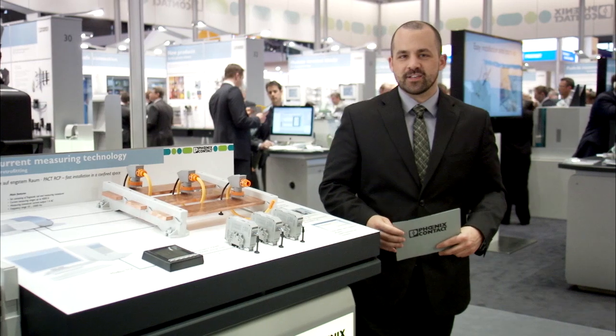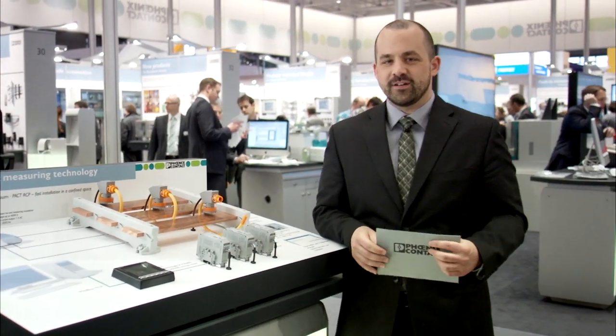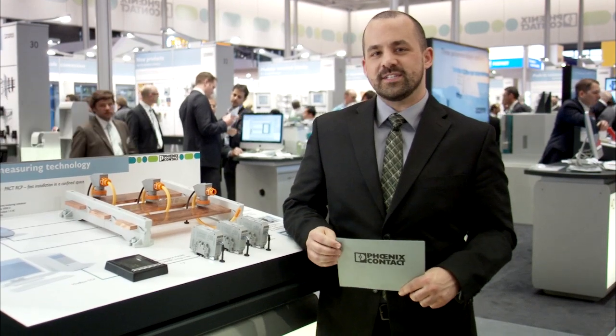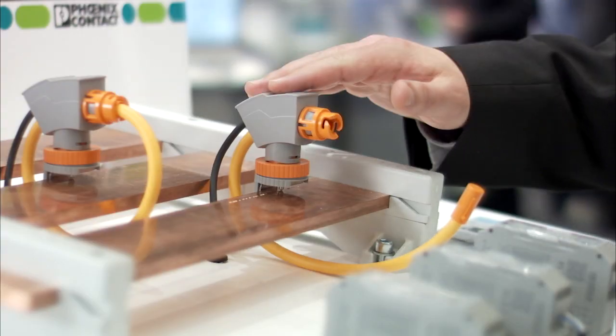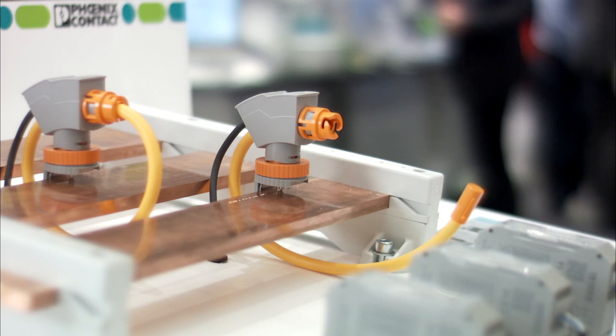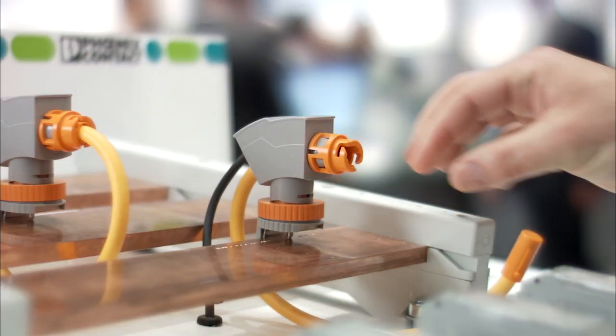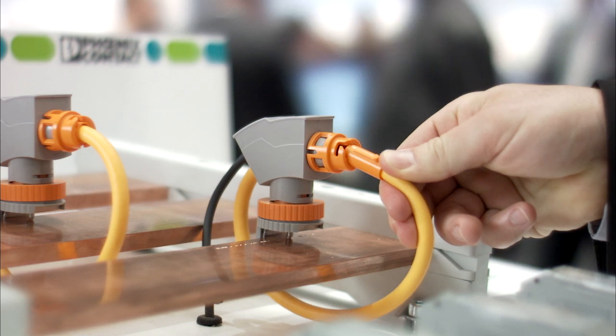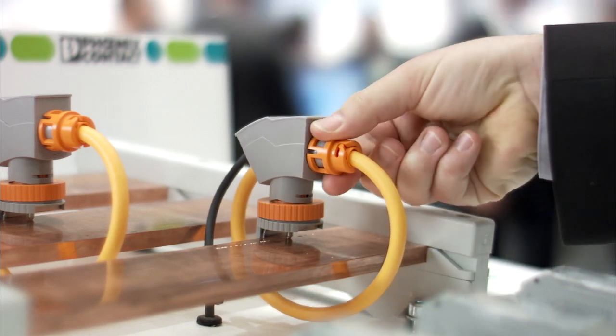Measuring energy flows has become increasingly important for energy efficiency and environmentally friendly operation of machines and systems. The new current transformers for retrofitting can be quickly and easily installed in places where the conventional split core current transformer doesn't have enough space. Put on the attachment, place the Rogowski coil around the bus bars, snap into place, and you're done.